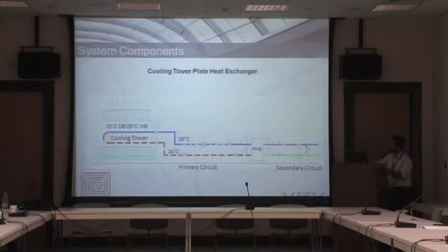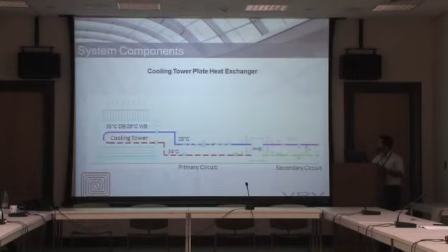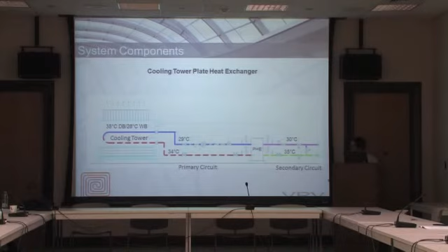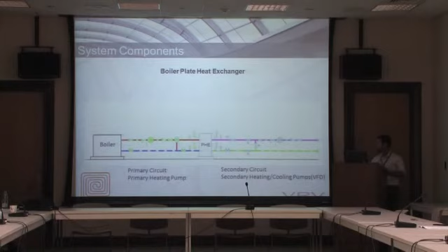It has a condenser pump connected to the plate heat exchanger. After the plate heat exchanger, there is the secondary circuit, the cooling or heating circuit. Whenever T1 exceeds 30 degrees, the two-way valve here will open and the cooling tower will operate. And the same goes for the boiler. We have a primary circuit and a secondary circuit with secondary heating and cooling pumps.